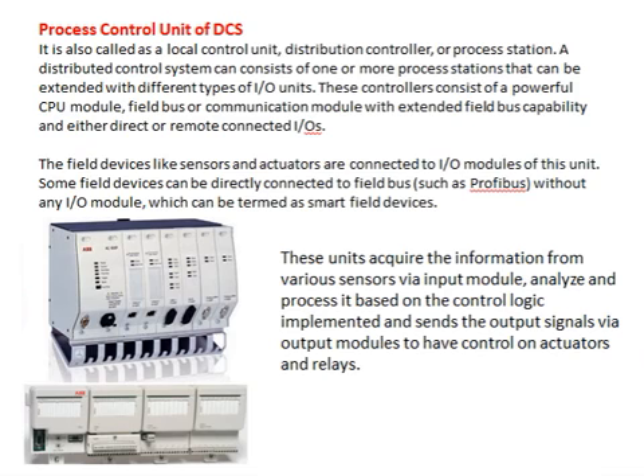Some field devices can be directly connected to a field bus, such as Profibus, without any I/O module, and are termed smart field devices. These units acquire the information from various sensors via input modules, analyze and process it based on the control logic implemented, and send the output signals via output modules to control actuators and relays.